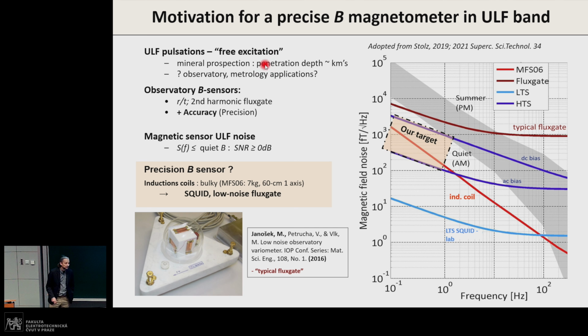Probably we can, and I will show, use these effects also in metrology applications. The typical observatory sensor, which measures not only magnitude but also orientation, would be a second harmonic fluxgate. There was a talk a few months ago by my colleague Wojciech Petrucha. Basically, observatories focus very much on accuracy, not much on precision or low noise of the sensor, but accuracy - calibration, establishing the true orientations of the vector matter.